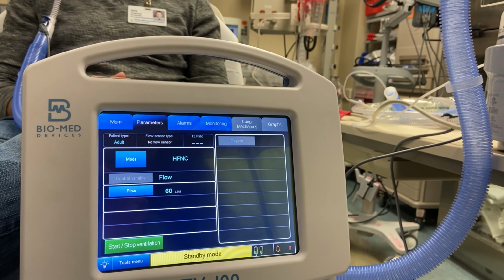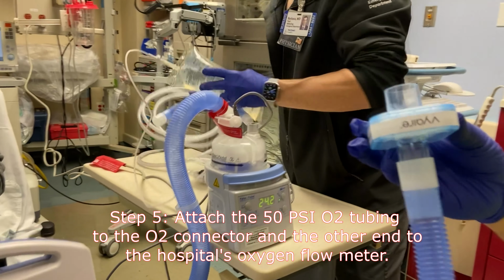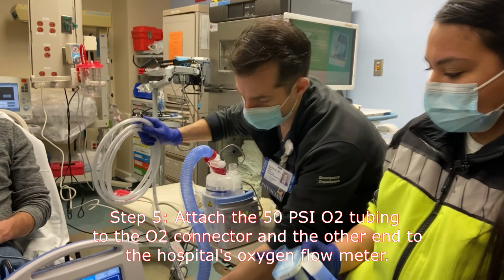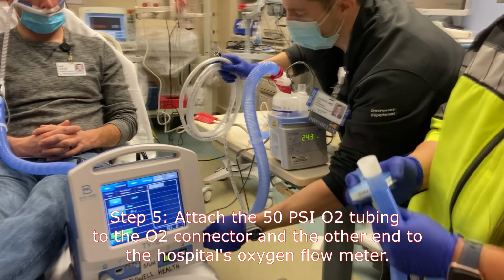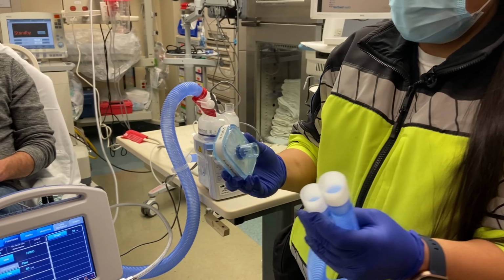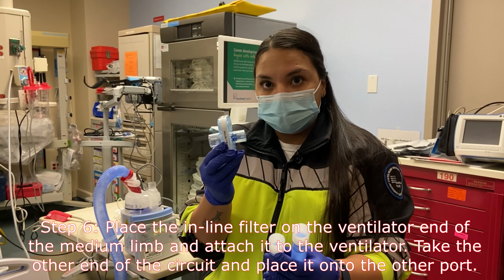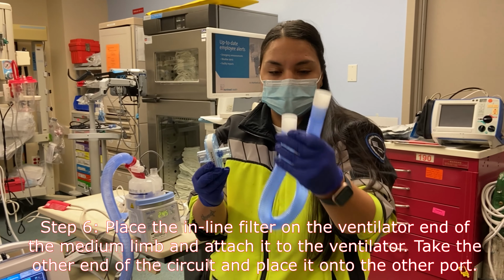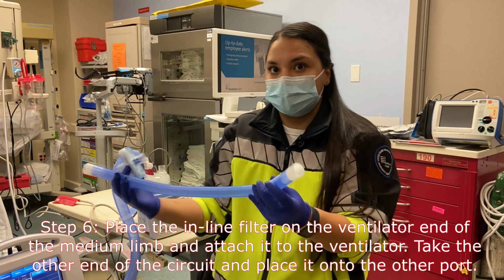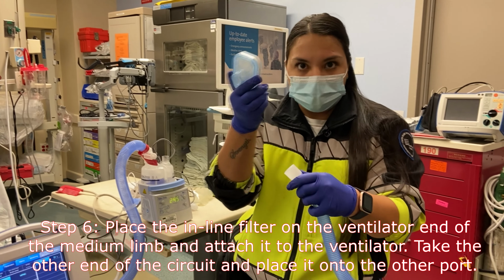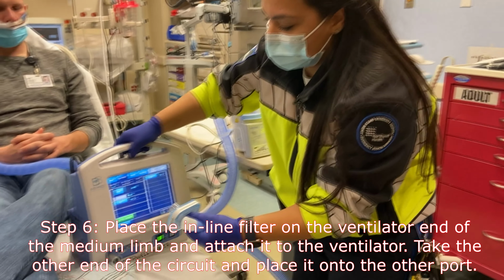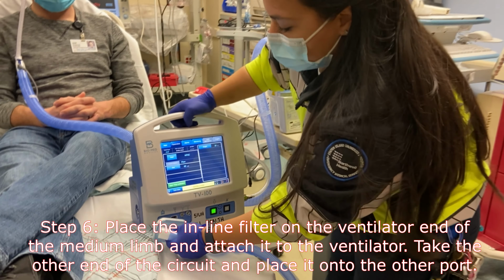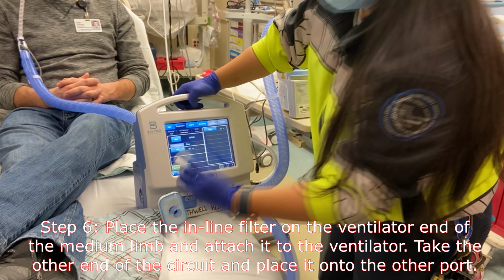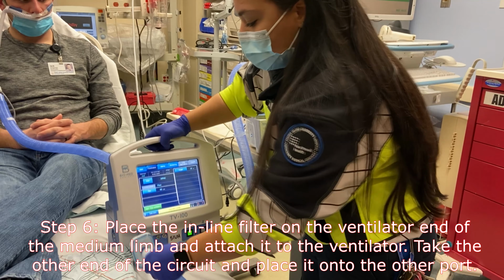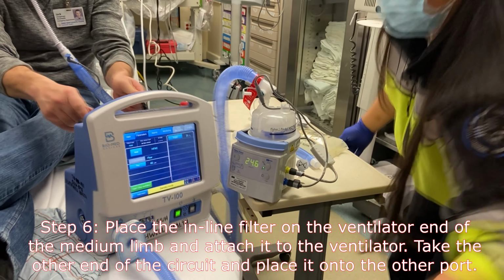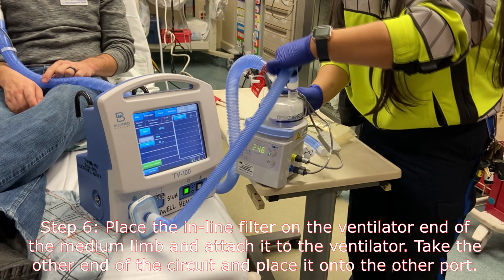I'm going to hook up the rest of the circuit, and I'm going to hook up the oxygen to the hard line here. So you can use the filter, it's just added protection, or you can just hook up the small line to the vent. But most of us will put the filter to the vent. So what you do is you take the filter on the end here, tubing through here. So this connection will go to the top here.